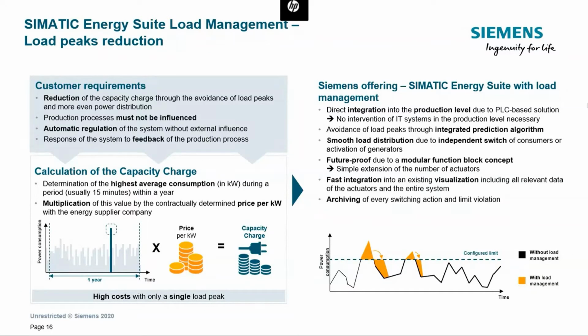Based on the measurements coming from your system, from your equipment, you can identify if the consumption is going to achieve or even go beyond a particular limit. Based on that information, the controller, the load management system can take actions in terms of maybe shutting down some loads or switching on a generator, additional sources of power, to try to avoid these additional charges for extra power consumption. This was introduced in version 16 of Energy Suite.